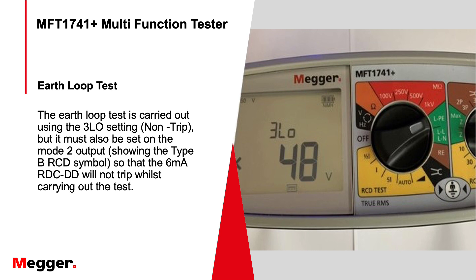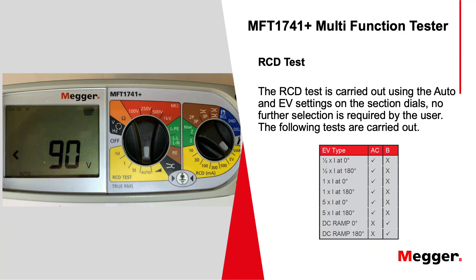For the earth fault loop test, set up as normal with the Megger on L-PE and Z — it automatically defaults to the low current setting because we're going through RCDs, so it needs to be a low current test. However, there's a second selection needed: press the scrolling key to select the type B symbol at the bottom. This is not saying it's doing a type B RCD test — we're reusing symbols — but this is the required setting to make sure the 6 mA RDC-DD isn't tripped.